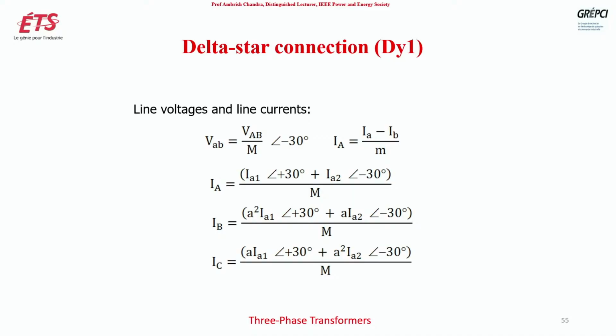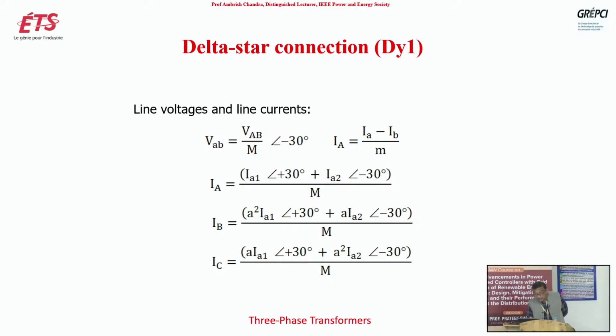Now if you see the line side of the current of DY1 transformer, if you have positive sequence current, then it will have plus 30 degree. It means the seventh harmonic will be shifted by plus 30 degree, while the fifth harmonic will be shifted by minus 30 degree. While in DY11 it was, seventh harmonic was shifted by minus 30 degree and fifth harmonic was shifted by plus 30 degree. So you have to see the difference. Okay, seventh harmonic plus 30 degree, fifth harmonic is minus 30 degree. So this is, we have seen.